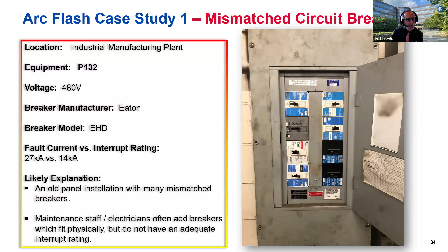So a mismatch breaker: in this case, you've got a coordination study situation where you'll have overlapping of the coordination. It's a different type of molded case circuit breaker, and the breaker settings may have been changed to avoid a tripping situation. This will prevent one breaker from tripping if a fault was to occur downstream of the secondary breaker. Making sure everything is coordinated and properly set so it performs as designed is another key component of the arc flash study.